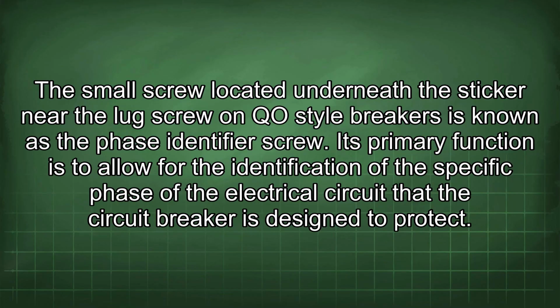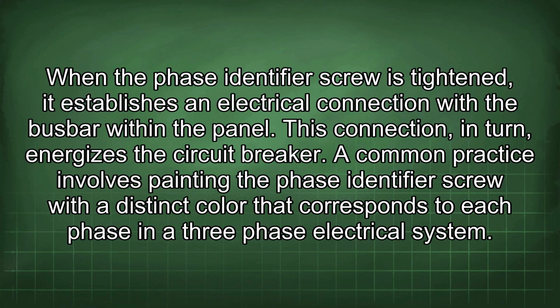The small screw located underneath the sticker near the lug screw on QO style breakers is known as the phase identifier screw. Its primary function is to allow for the identification of the specific phase of the electrical circuit that the circuit breaker is designed to protect. When the phase identifier screw is tightened, it establishes an electrical connection with the busbar within the panel. This connection, in turn, energizes the circuit breaker.